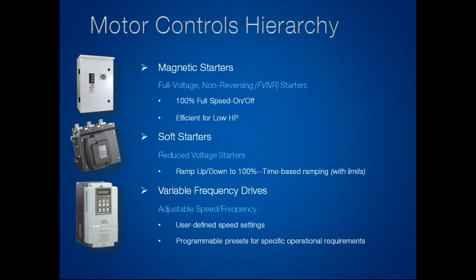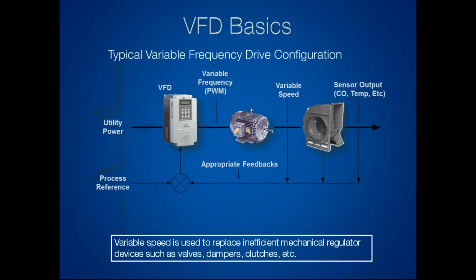And then finally, we have our variable frequency drives. Our variable frequency drives are essentially able to modulate the frequency of the motor. So the VFDs are just speeding up and slowing down our motors based on what you're telling it to do. Drive is kind of a funny term, right? Think about driving a car. A drive is like a gas pedal, okay? With your gas pedal, you're just telling your motor to speed up or slow down based on certain conditions in your building.